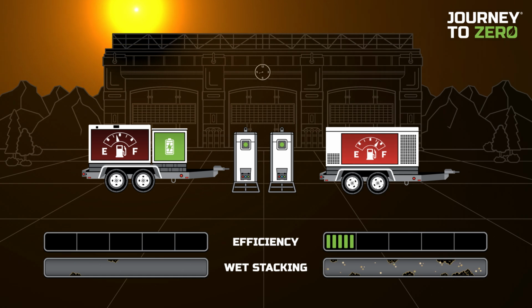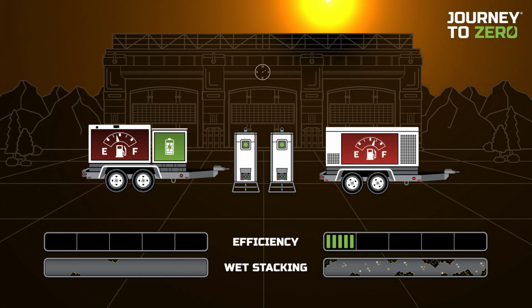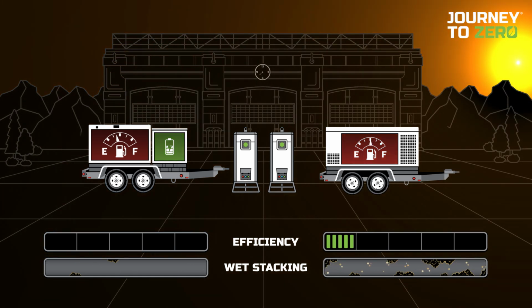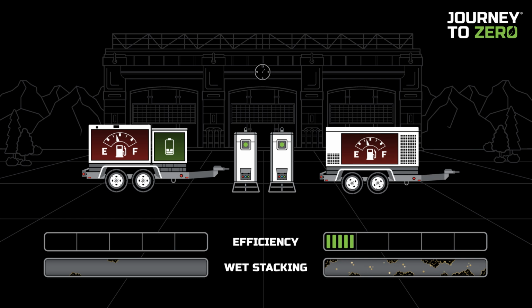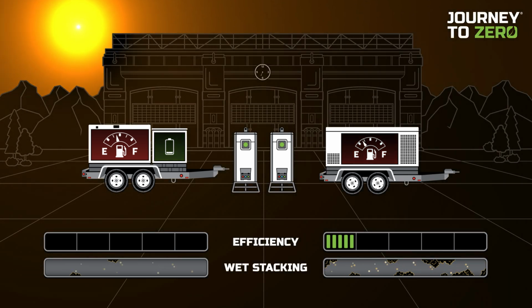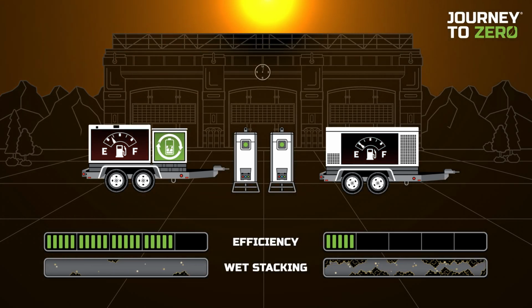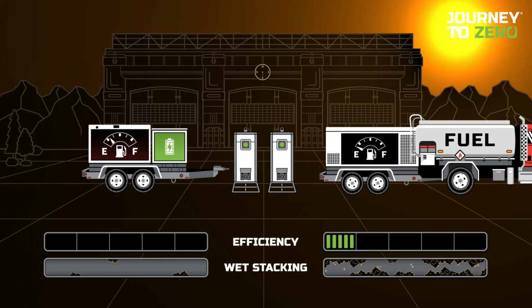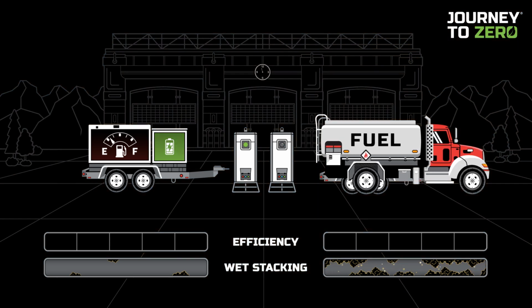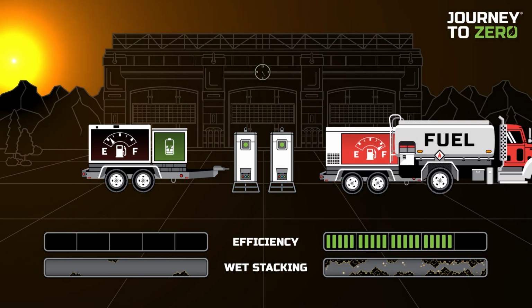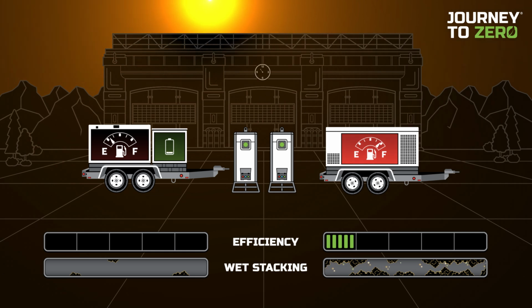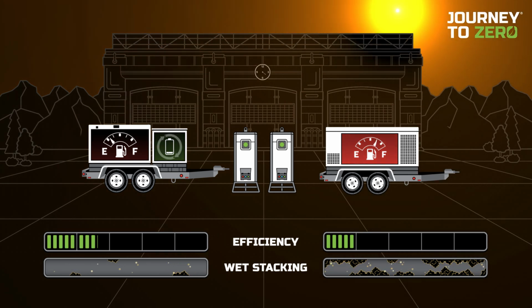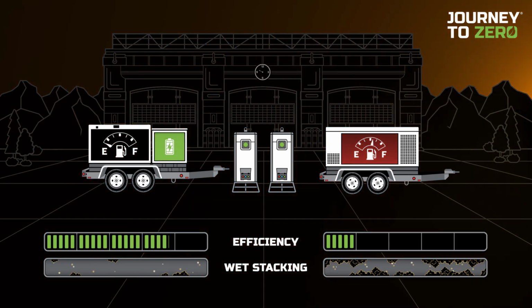The EBOSS is fuel efficient, using up to 80% less fuel compared to a conventional diesel generator. On a typical application, a traditional generator would need to refuel 2.5 times on a site before the EBOSS would require refueling. With the EBOSS, the diesel engine consistently operates at peak efficiency, reaching optimal temperatures each time it charges the battery, reducing light loading and wet stacking.